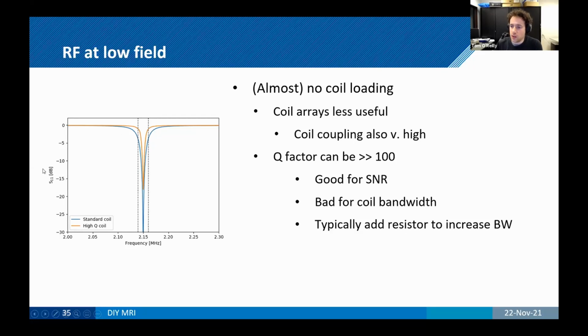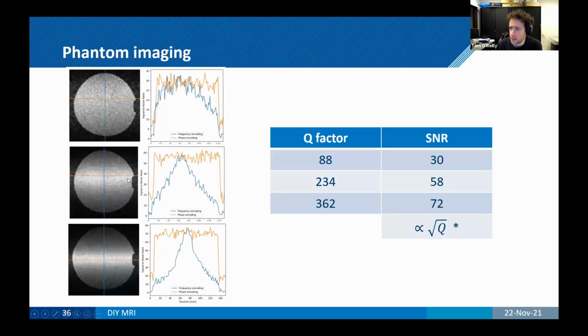Just to show you, these are some S11 plots of a solenoid, like a decent solenoid, which is the orange one, and then the blue one is the standard one that we use for imaging, because we need to acquire signal from within the region marked by the black dotted lines, right? So if we look at the high Q coil, we're essentially not picking up anything by the time we get to the edges of the field of view. And you really see that coming back in images here.